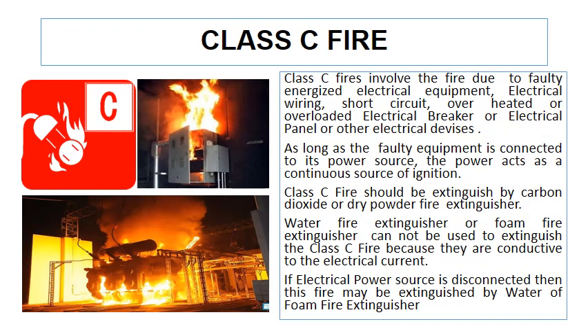Class C fires involve fires due to faulty energized electrical equipment, electrical wiring, short circuits, overloaded electrical breakers, electrical panels, or other electrical devices. Class C fires are very common in both homes and industrial premises. As long as the faulty equipment is connected to its power source, the power acts as a continuous source of ignition. Class C fire should be extinguished by a carbon dioxide fire extinguisher or dry powder fire extinguisher. Water or foam fire extinguishers cannot be used on Class C fire because they are conductive to electrical current. If the electrical power source is disconnected, then this fire may be extinguished by a water or foam fire extinguisher.